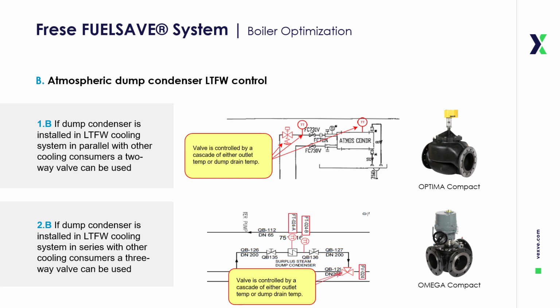On the other hand, if the dump condenser is installed in series with other cooling consumers, a three-way valve is required. In this configuration, the valve diverts flow either through the condenser or bypasses it, depending on system demand and temperature conditions. For these applications, Frese offers both the Optima Compact and the Omega Compact valve solutions. By selecting the appropriate valve configuration, two-way or three-way, depending on the condenser's placement in the LTFW cooling system, the Frese FUELSAVE system ensures precise control of steam condensate temperature, minimizing fuel consumption and improving overall boiler efficiency.